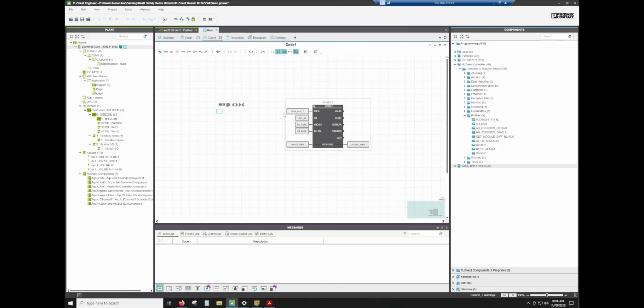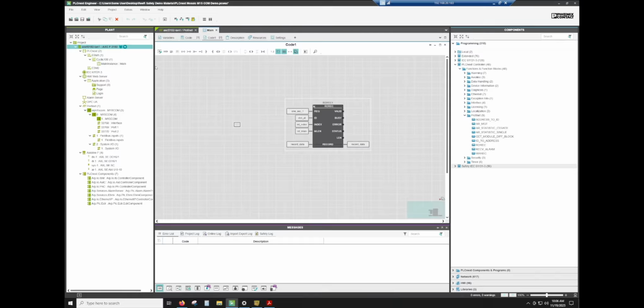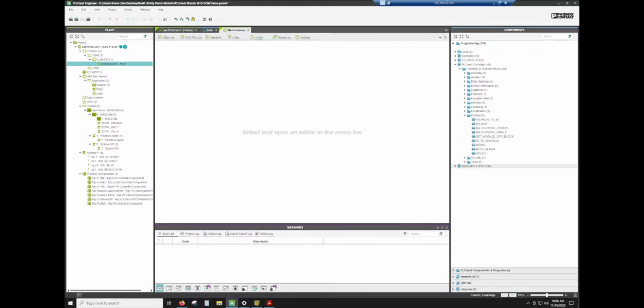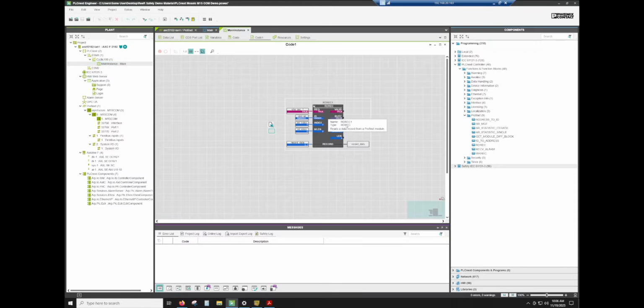All right, now that we have this all set up in Profinet, again, I already have this program mostly built, so we're just going to go online with it just to see what happens. So we go here, we're already connected to the PLC. We're going to do debug mode. We're going to open the main code. We're going to look at code 1. This is where our record data is being asked for. So again, if we look here, this is actually 13 because 13 in hex is 19 in decimal. And then the index and the maximum length are in decimal.